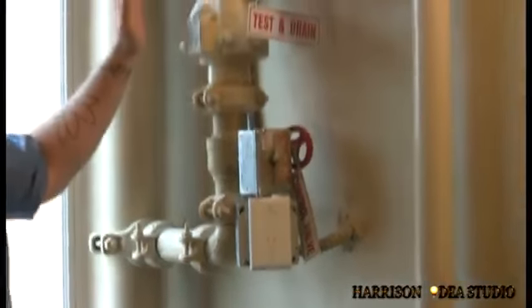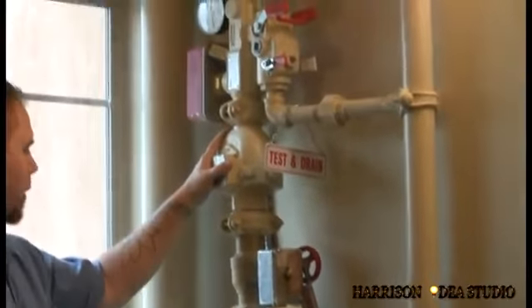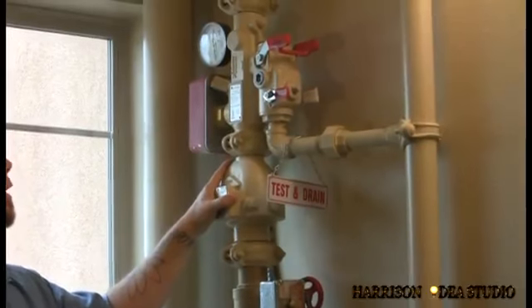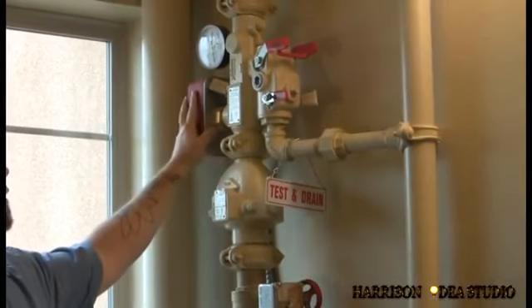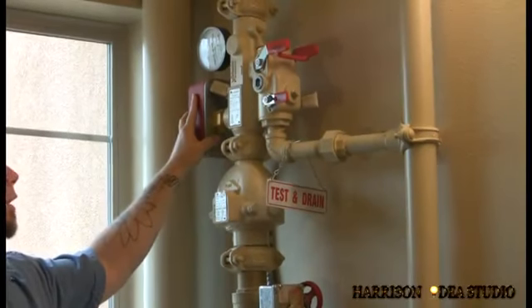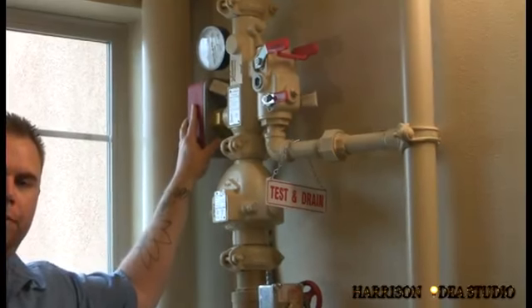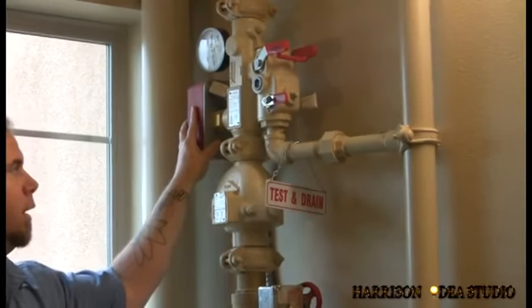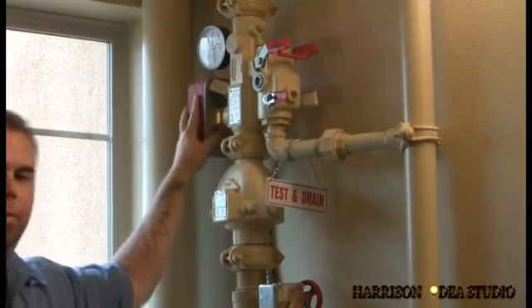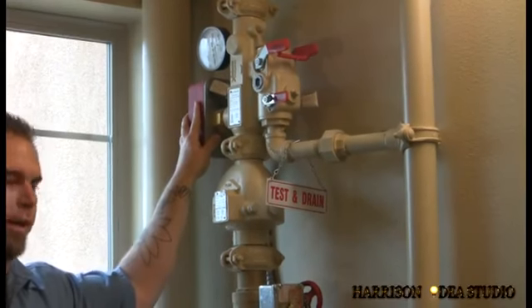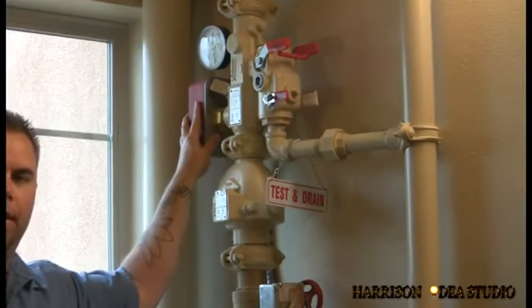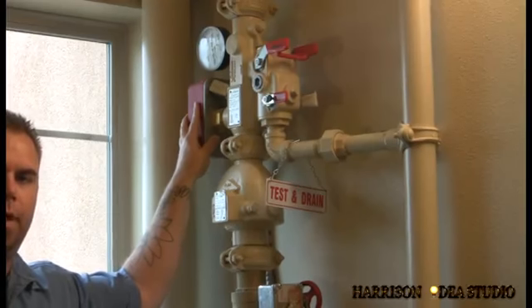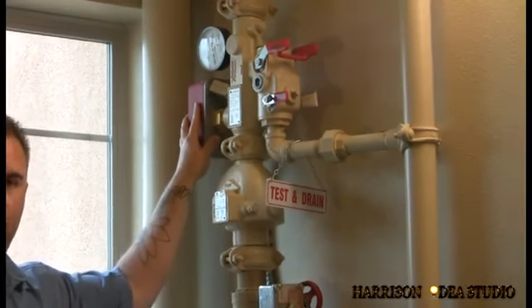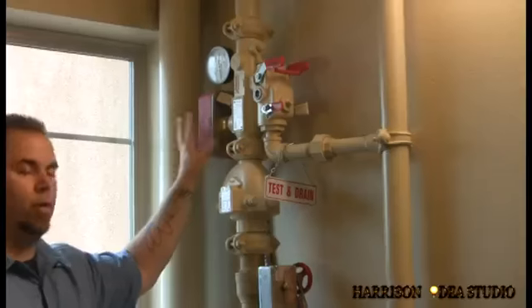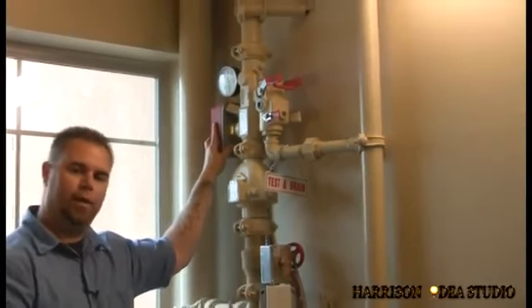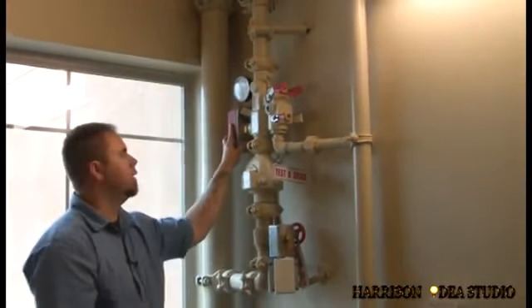Just above that is your check valve so that the water doesn't go backwards into the city water main. You've got your flow switch, which indicates flow out of a sprinkler. If a sprinkler were to discharge, this would pick up that water flow, sending a signal to your alarm panel and notifying the fire department that there's a fire on the third floor. We're on the third floor now. Every floor has this as well, so they can determine where the fire would be.